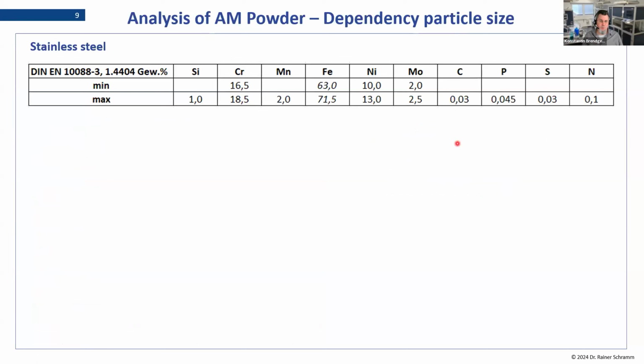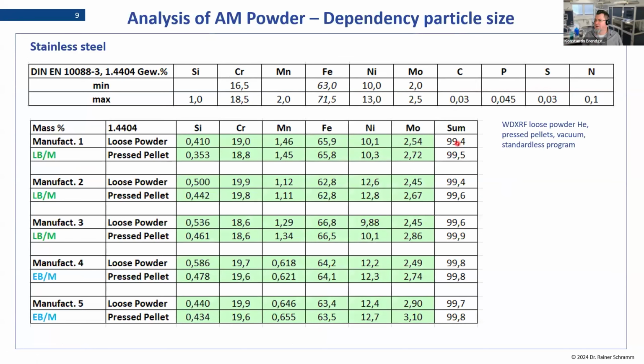It was the results. We then checked the loose powder and compared it to a pressed pellet. And so what we see here is, for all 5 materials, we have the loose powder on top and the pressed pellet, and we use the same standardless software to analyze this on our wavelength dispersive unit. So standardless meaning we just told the software what this is, and then the software made the analyses for us, and it's the same program that does the analysis. And as you can see, the differences between the pressed pellet and loose powder are quite small.